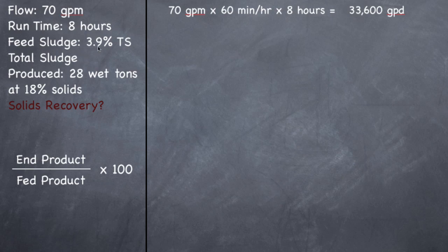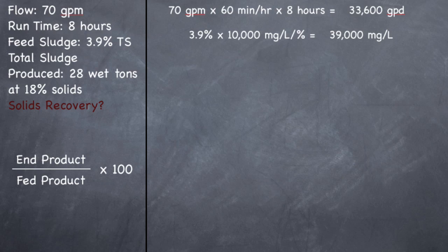The feed sludge is 3.9% total solids. Before coagulation, a sample was taken to find out how much was total solids — it's 3.9%. Remember, 1% is 10,000 milligrams per liter. So 3.9% times 10,000 mg/L per percent gives a concentration of 39,000 milligrams per liter. So the feed sludge is 39,000 mg/L.